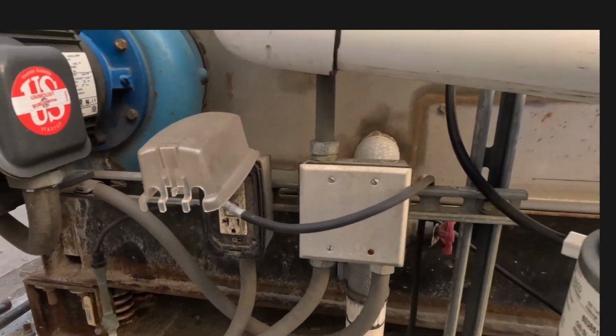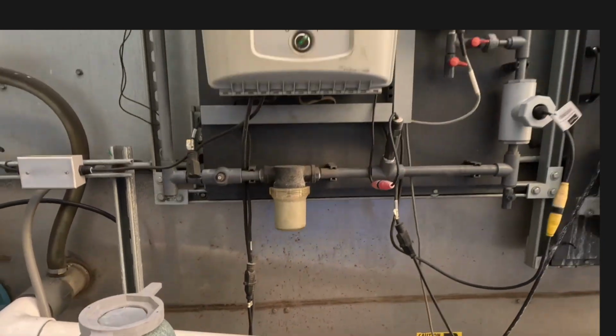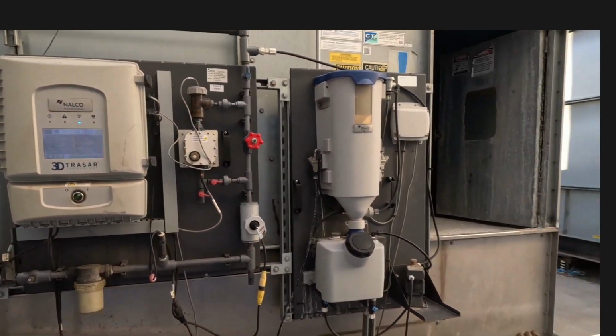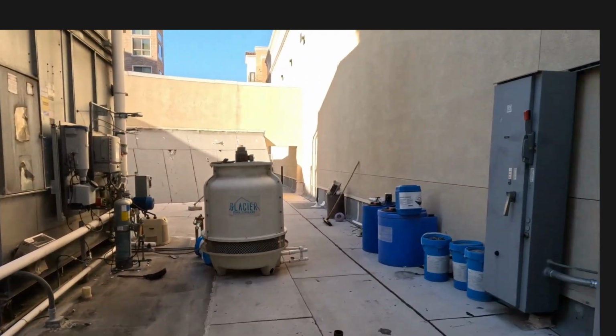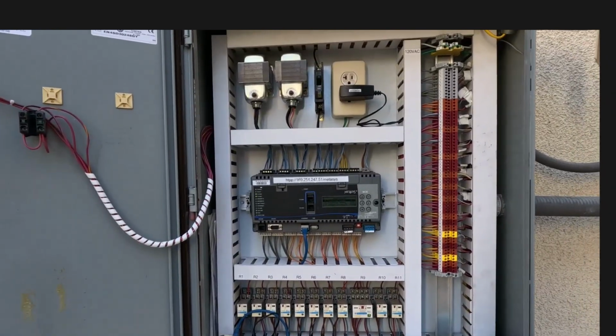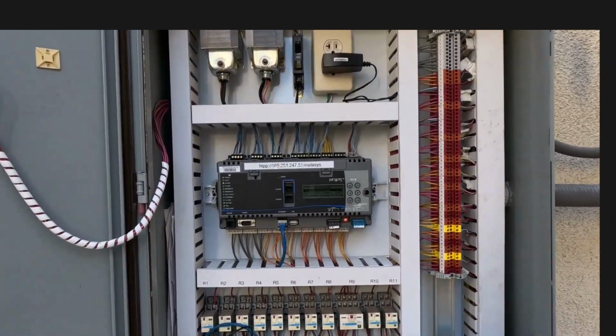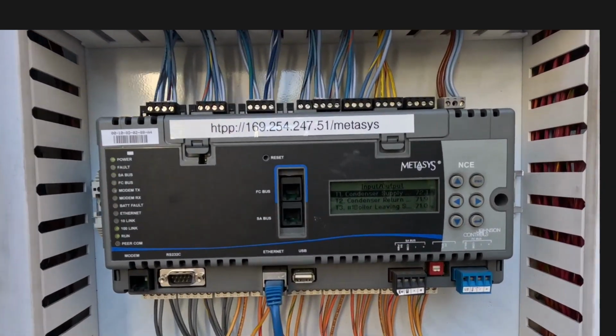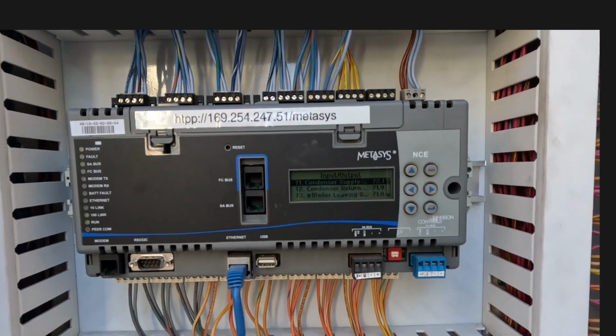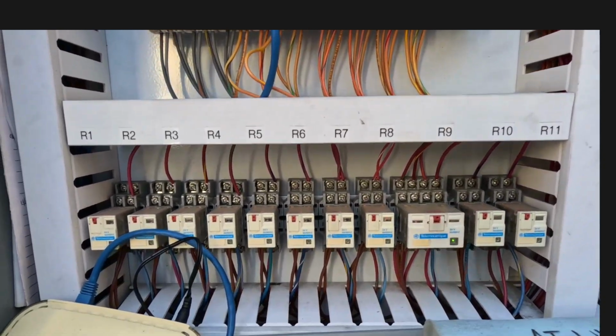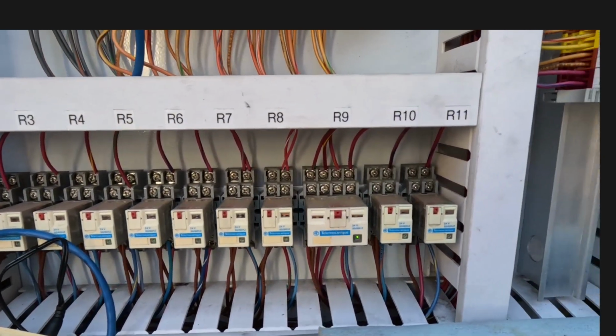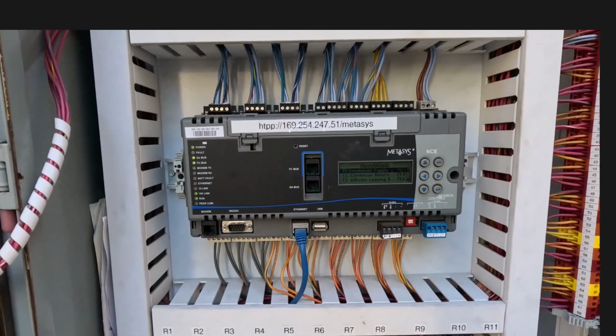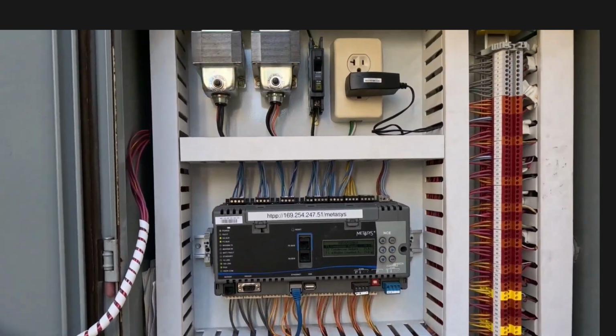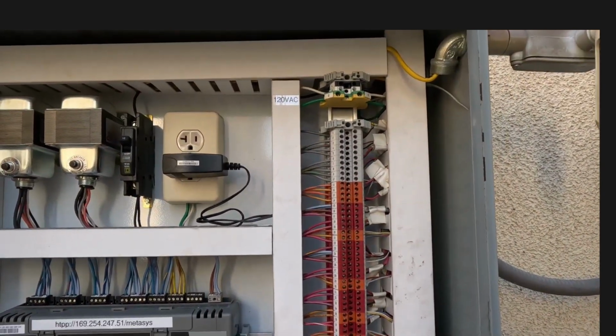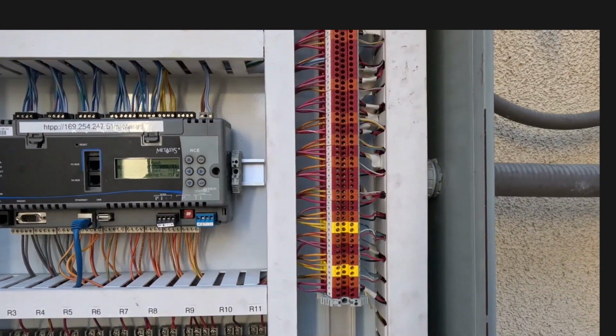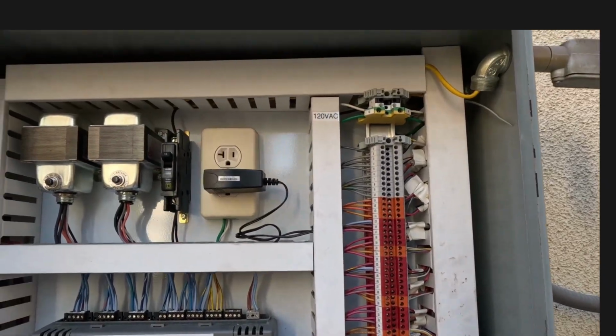And it's providing power for your chemical station here. This is the control center of this system. As you can see, this is the main controller that controls all the devices, and then a series of relays here that get triggered when this controller says to do so. And then you've got a terminal block here with all the wires on the control side of things.